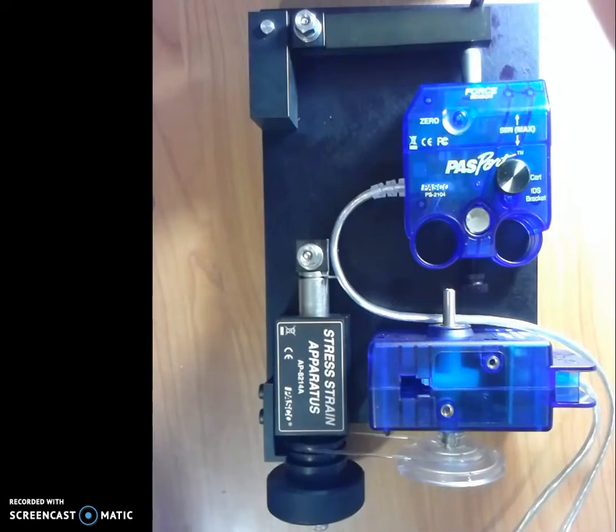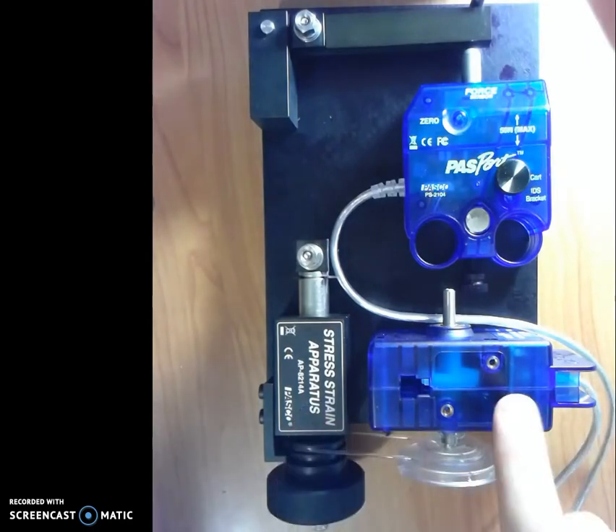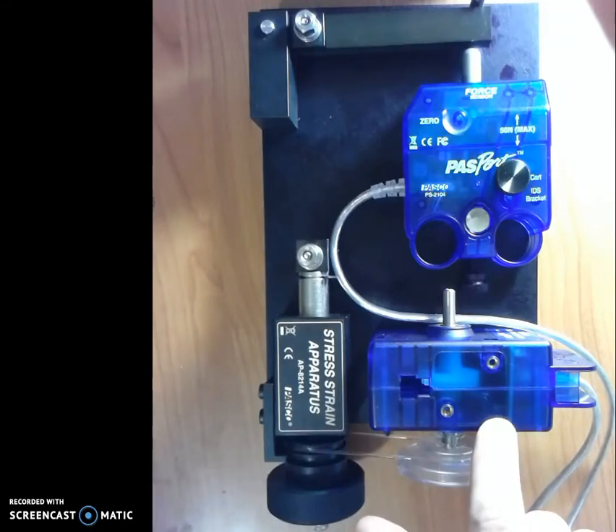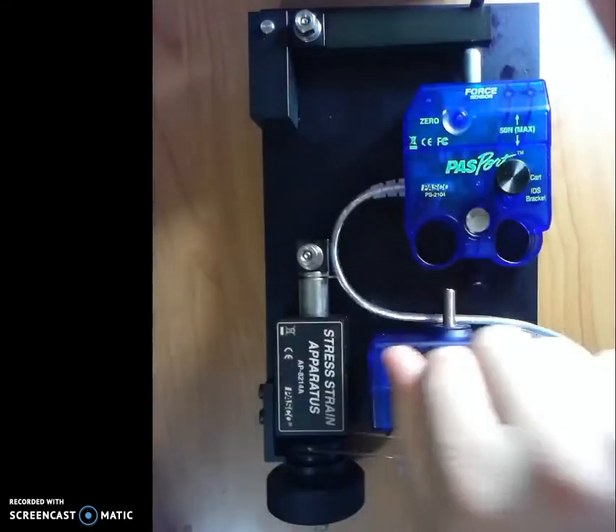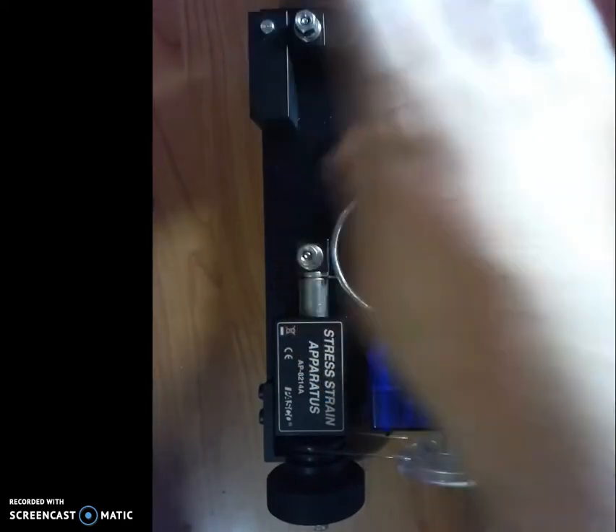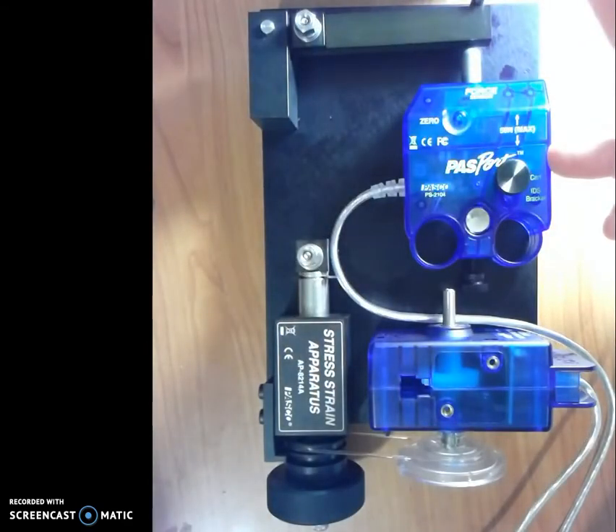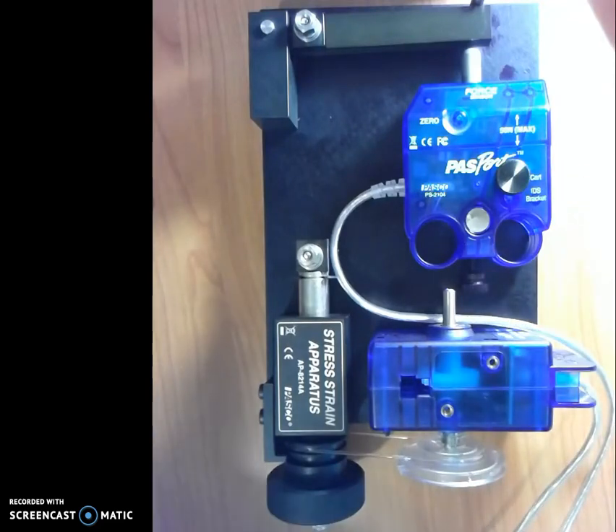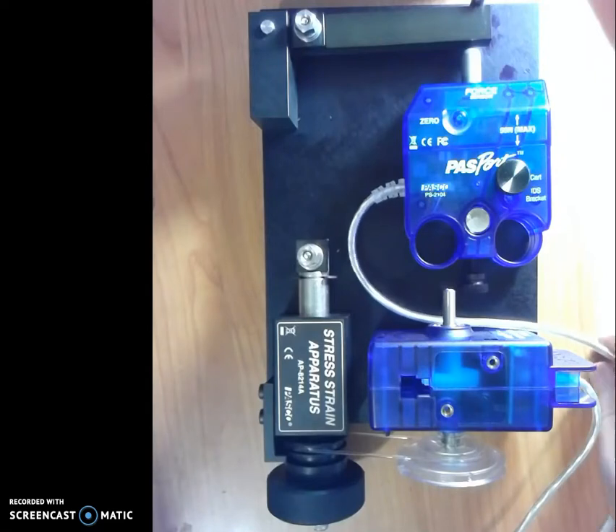This is the fourth video in my series on how to assemble, calibrate, and take data from the PASCO stress strain apparatus. We've now installed the rotary to linear actuator. We've installed the sensor that detects how many times I've turned this and turns that into a linear displacement. We've installed the lever here, which converts the displacement and the force on the sample, which will go here, into something that can be measured by the force sensor. We've installed the force sensor. We plugged everything into the data studio, to the PASCO 850 universal interface, and now we are ready to start taking some data.